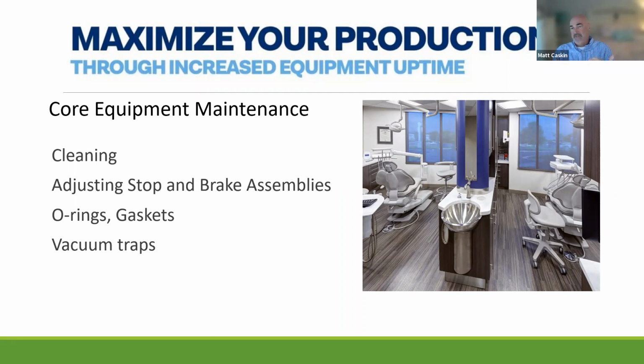These adjustments on all of this equipment, it's typically very simple. Again, there's Allen screws and stops on all these pivot points. They do loosen up over time, and it's usually just a quick adjustment. So don't live with the aggravation. You guys spend a lot of time in these operatories. You want to make sure that you're keeping them functioning as they should, like new.